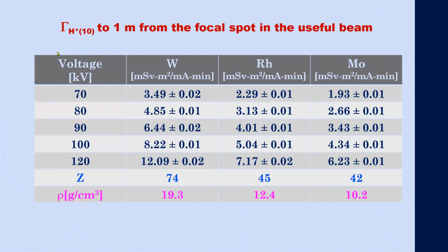So in this table, I am presenting you the gamma factor for the ambient dose equivalent at 1 meter from the focal point, for the focal spot in the useful beam. And here is the information when the target is tungsten, when it's rhodium, and when it's molybdenum, in terms of the high voltage. Notice that the gamma factor is expressed in millisievert square meter per milliampere per minute. The minute means the time in minutes that the X-ray beam is on. The milliampere is the current that we use in our X-ray tube. The square meter is the distance in meters from the focal spot to the point of interest. And those are given in millisievert because we are expressing here the ambient dose equivalent.